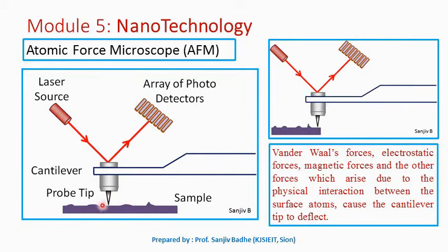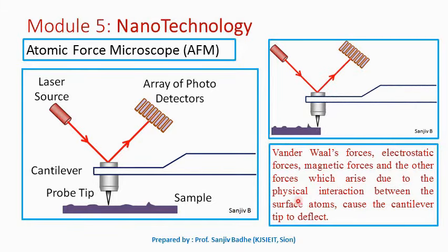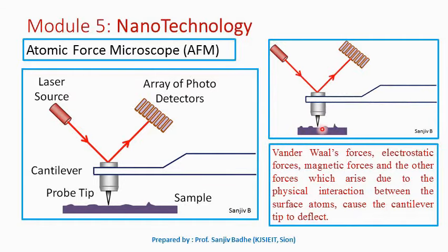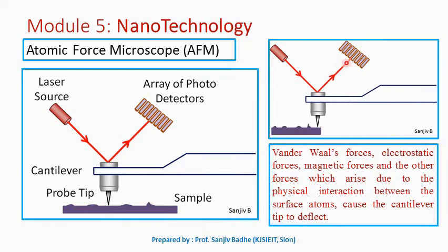When the cantilever tip is brought into proximity of the sample surface, forces such as Van der Waals forces, electrostatic forces, magnetic forces, and other forces arising due to physical interaction between surface atoms cause the cantilever tip to deflect. As the cantilever tip is deflected, the angle of the mirror will change, and depending on the change in angle, the reflected light ray will change direction.